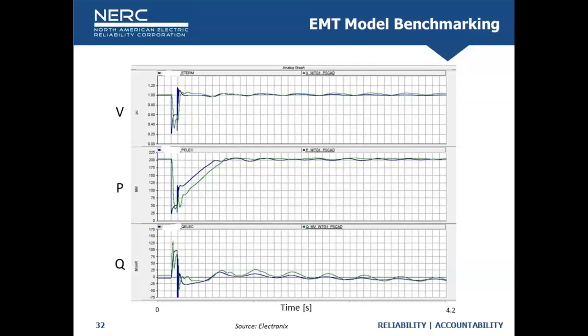The first thing to touch on is model benchmarking, using EMT models to ensure the positive sequence models are sufficiently accurate. You can see a fairly good match here. You don't expect the EMT model to match the positive sequence model time step by time step, because of different simulation techniques, modeling assumptions, and controls modeled. But if you blur your eyes a little, the oscillation magnitudes and ring-down match fairly well, the active power recovery matches quite well, and the voltage dip during the disturbance matches quite well.